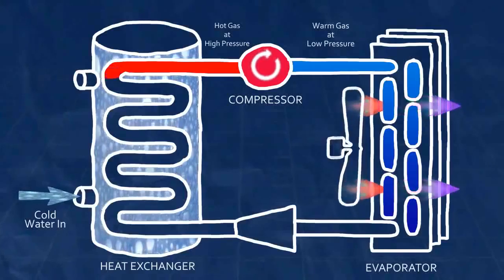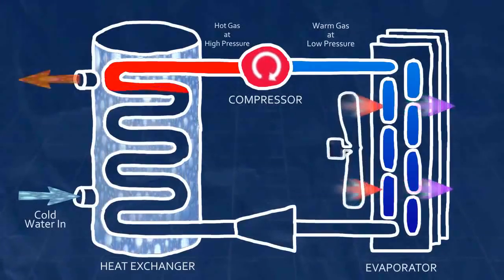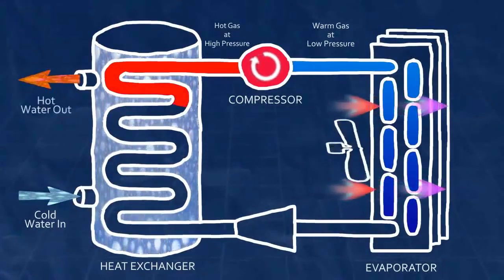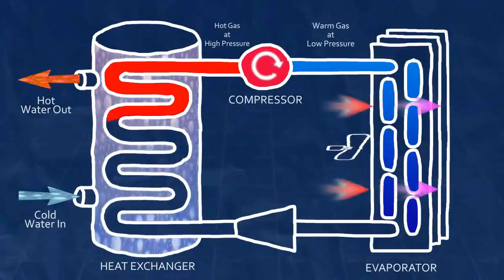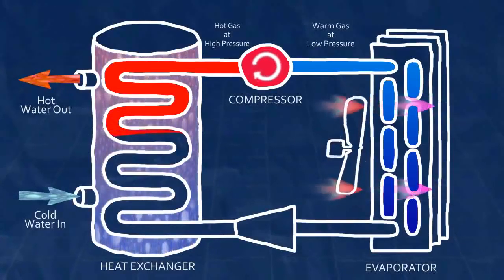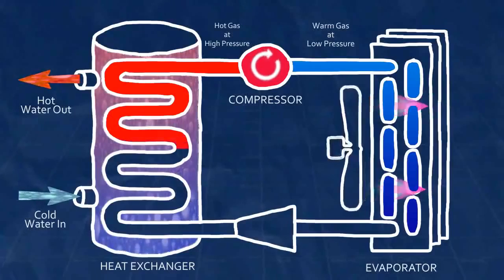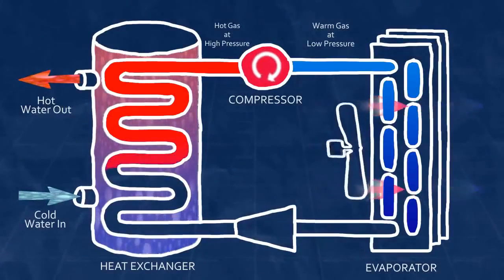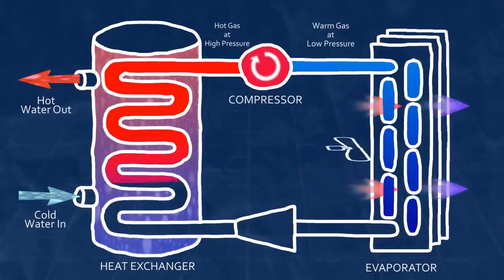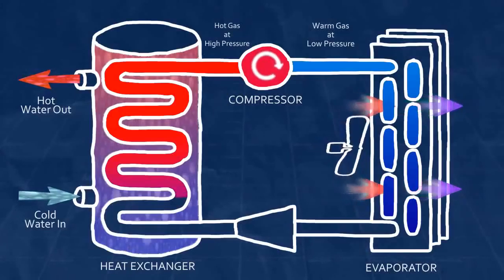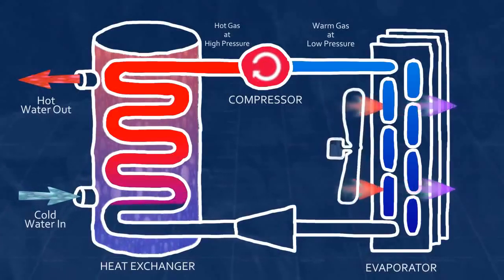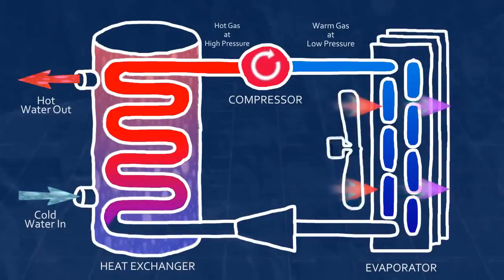The condenser is in contact with the water and the hot gas now gives up its heat to the colder water. As heat leaves the gas refrigerant, it cools off below its condensation point and changes from a gaseous state to a high-pressure liquid state. The change from gas to liquid facilitates the large transfer of heat energy to the water.